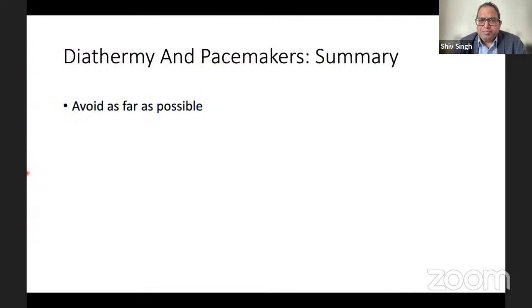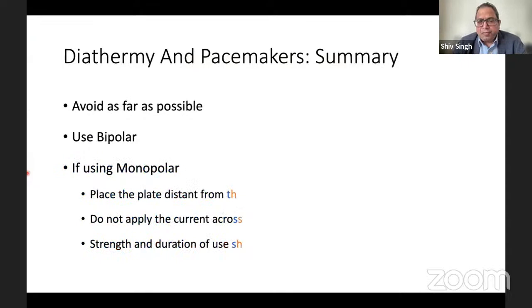And if you need to use it, use bipolar. But if using monopolar, you need to have the plate or the indifferent electrode placed as far as possible from the pacemaker unit. And do not apply current across the chest. And the strength and duration of use should be minimal. It should be used in very short bursts. So don't use cutting. Coagulation might be okay.